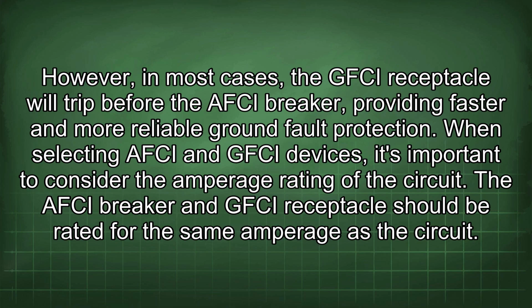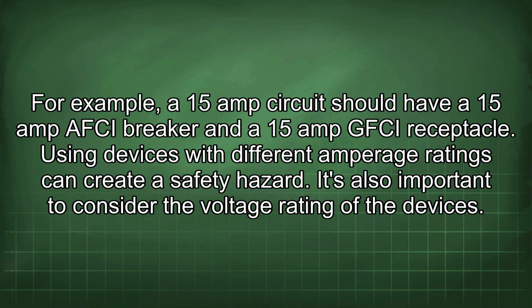When selecting AFCI and GFCI devices, it's important to consider the amperage rating of the circuit. The AFCI breaker and GFCI receptacle should be rated for the same amperage as the circuit. For example, a 15 amp circuit should have a 15 amp AFCI breaker and a 15 amp GFCI receptacle. Using devices with different amperage ratings can create a safety hazard.